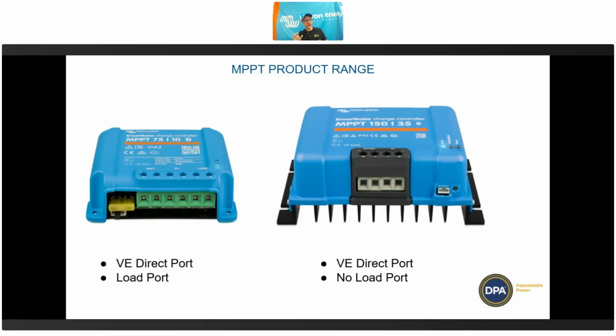So that's really useful on small systems, again, like security cameras and things where you don't want to have separate bits. It's just an all-in-one device. But when you get larger, then the current is too large and you wouldn't want to have it done internally like this. So the largest that they make in this format of having the 6 terminals is the 100/20. And after that, it's in the style that we have on the right-hand side here. And it doesn't have a load port. It's just got a battery and it's got a PV port. The smaller ones also have a built-in fuse, which is handy as well. And that's just protecting the battery terminals.